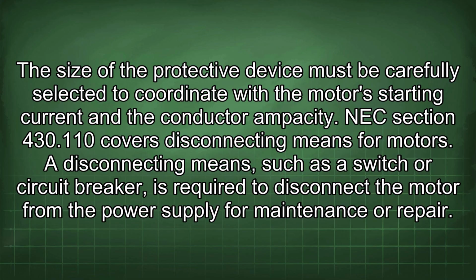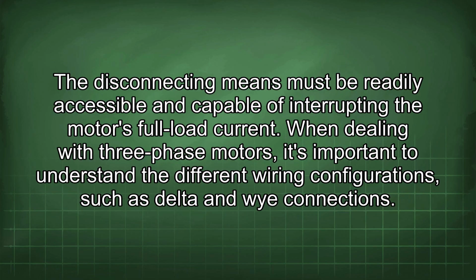NEC Section 430.110 covers disconnecting means for motors. A disconnecting means, such as a switch or circuit breaker, is required to disconnect the motor from the power supply for maintenance or repair. The disconnecting means must be readily accessible and capable of interrupting the motor's full load current.